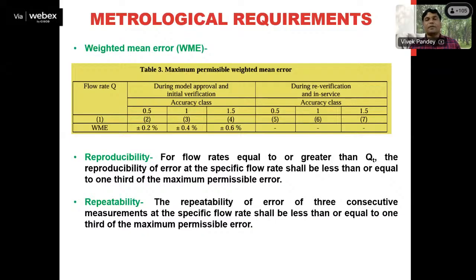So at 100 liter per hour, we have made a transaction of 1000 liter of gas. Then at 200 liter per hour, we have made the transaction of 1000 liter of the gas. So the quantity is the same, but it is being transferred through the same gas meter at different flow rates without changing the environmental parameters, I must say. That means the rated operating condition must be the same. So at all these different flow rates, the same quantity of the gas is transferred with the same gas meter.